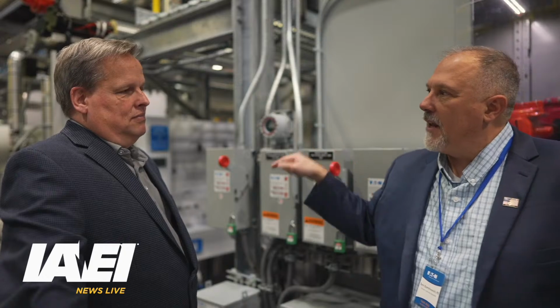If I'm working on a light, do I rely on the light switch as my disconnect? Can I rely on my light switch? Can I lock and tag a light switch out? I mean, as an electrician, you're carrying a belt and you're going into a dwelling unit. Do you turn the light switch off and go, all right, now I can work on this because it's de-energized, or do you go back to the breaker? Well, whatever you're going to do, it should be locked and tagged out. Right. And so they do make kits to go onto a snap switch to tag that out. Yep, they do, although not too many people have those laying around. I would go back to the breaker and turn it off.